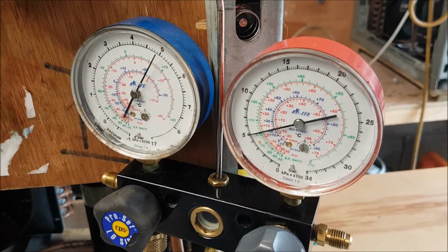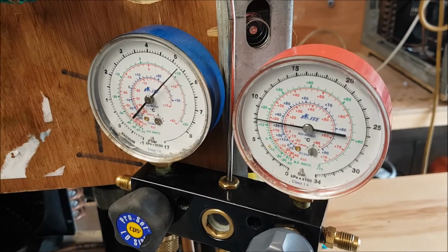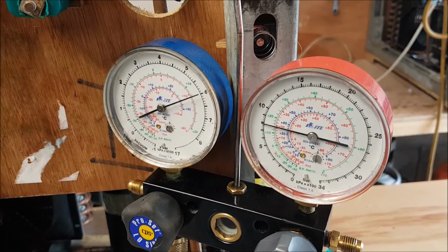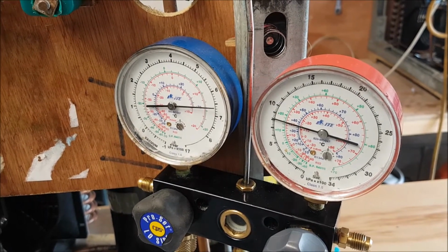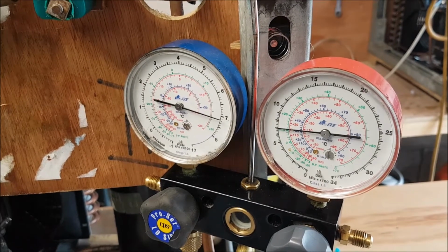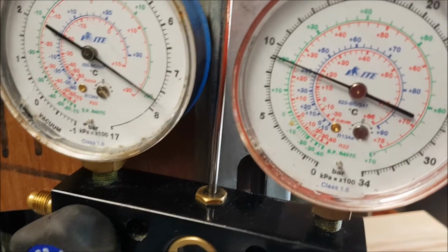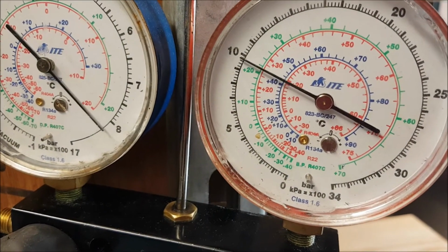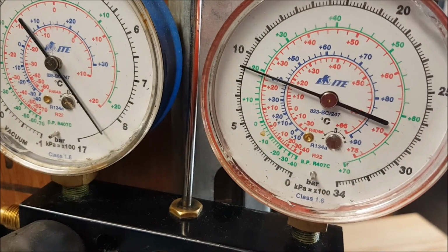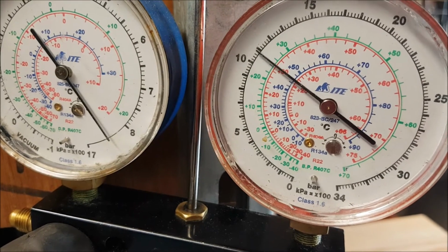And the reason for us to do that is because if it's going to leak, that's the stage where it's going to leak, at around 10 bar. So that might reveal a subtle leak. Now, the longer I can leave this under pressure, the better it is to detect an actual leak. So we've got the 10 bar there on the high side, just above. Get it up to 10 bar.